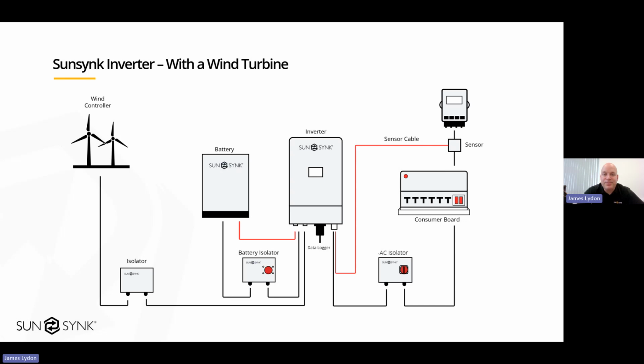With a wind turbine, there's a couple of bits missing on this. So with a wind turbine, it typically produces 3-phase noisy AC. That 3-phase noisy AC would then come into a wind controller or a rectifier before it gets to us. And that would change the 3-phase noisy AC to DC, and the DC would then connect into one of our MPPTs. And also built into that wind controller, you would typically have what's called a dump load.